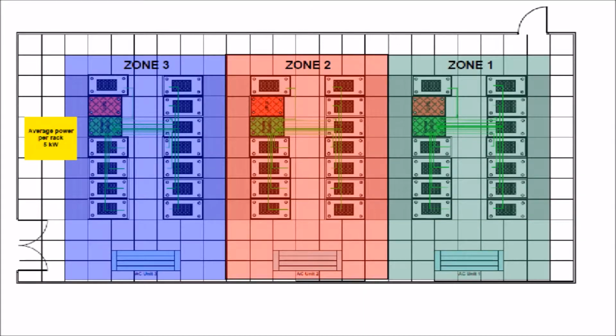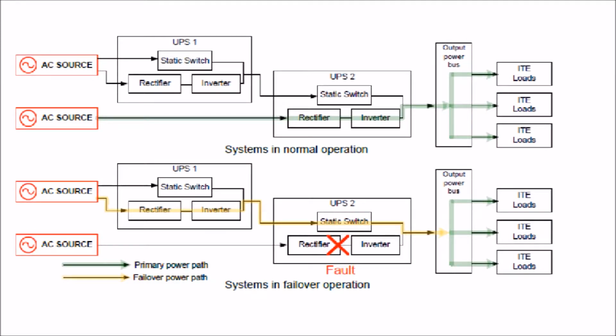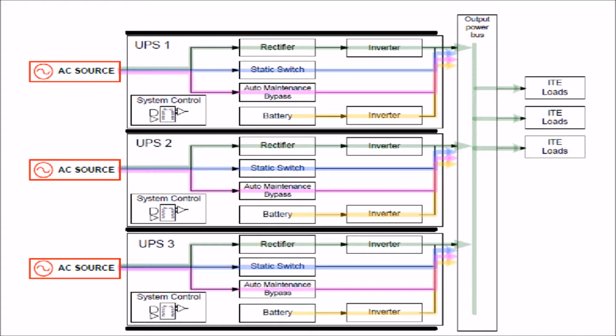This figure showing zone protection uses separate protected zones, and may use virtualization software to shift loads to other zones during failures or maintenance. Each zone has its own 60 kilowatt UPS system. Serial cascade UPS architecture with changing power path if the UPS under load fails. In this figure, the upper example is for a system in normal operation, and the lower is for the system in failover operation. In the shown figure, parallel UPS systems all feed the output bus, so any single UPS module can be isolated for maintenance or in case of a failure. Parallel systems must be synchronized together to share the loads.